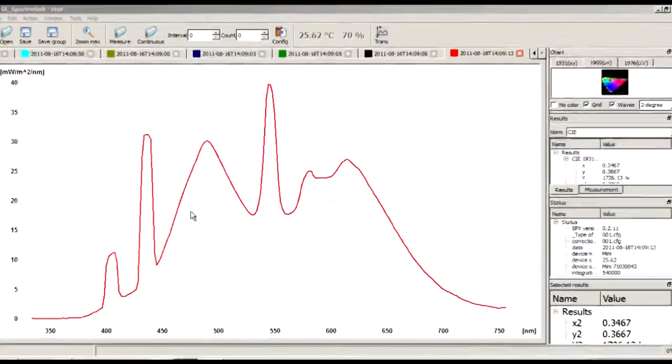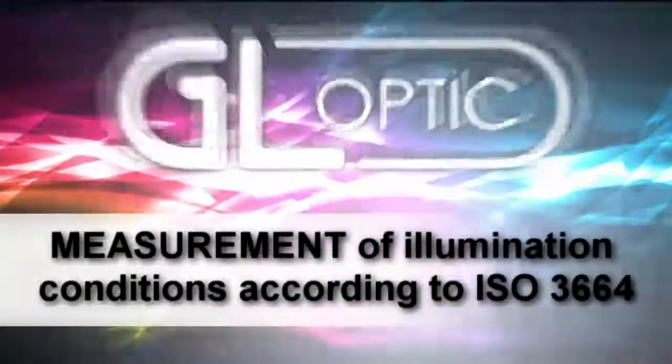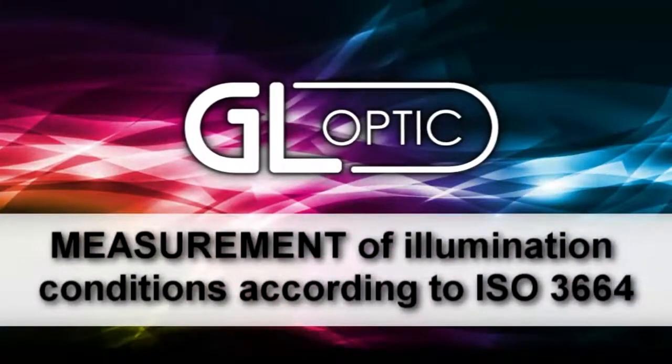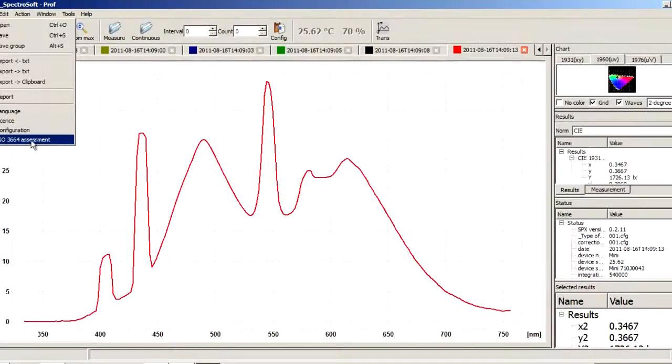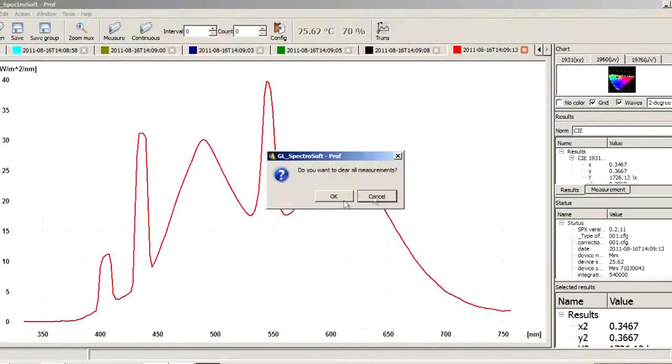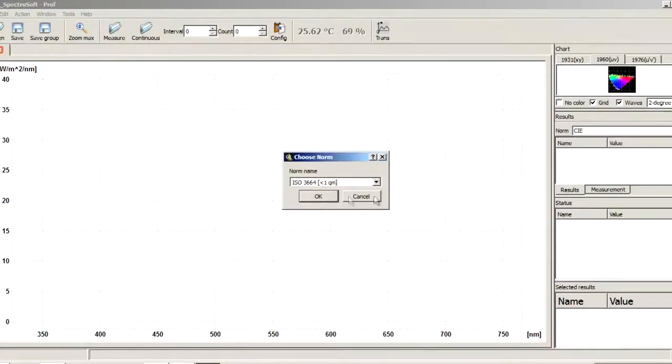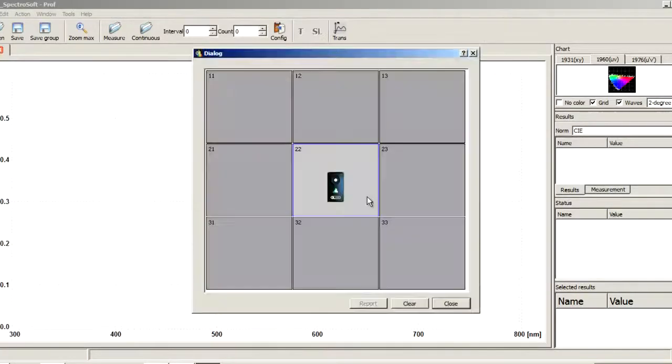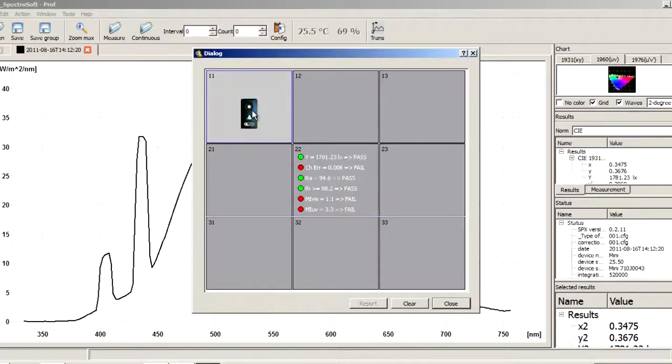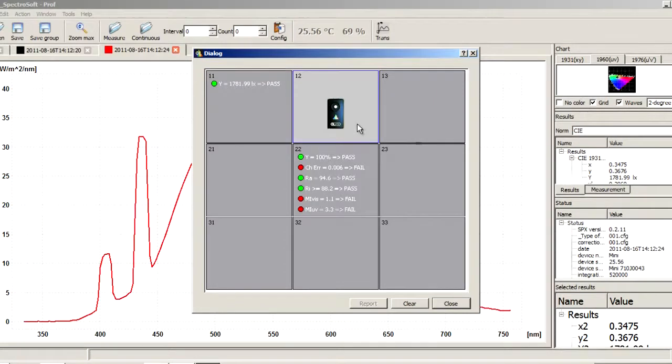GLOptik Mini Spectrometer features a user-friendly pre-configured mode for the assessment of light installation according to ISO 3664. It features the option for illuminated areas less than one square meter and above one square meter as required by this standard.